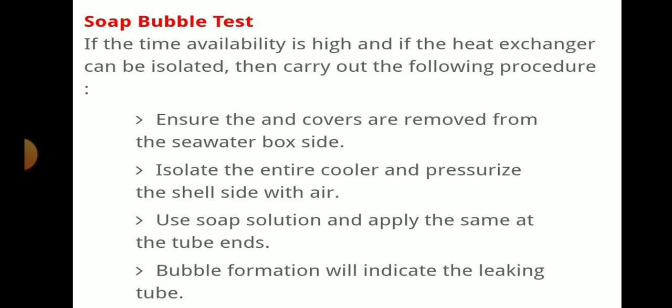Isolate the entire cooler and pressurize the shell side with air. Use soap solution and apply the same at the tube ends. A bubble formation will indicate the leaking of the tube.